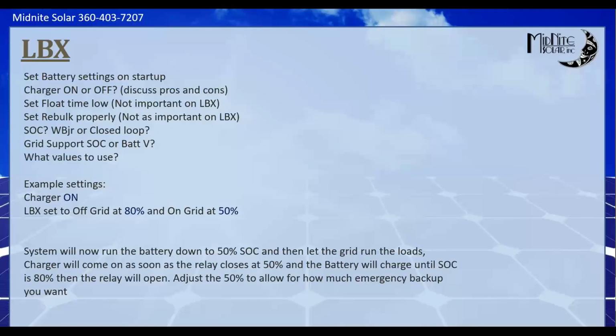I will say this: we've got one running in Oregon that's been running for over a year in grid support mode, and the utility came out the other day and said over the course of 12 months they have logged 0.14 kilowatt hours of selling from the Rosie, and they're monitoring 100 times a second. My utility in Florida has never noticed it at all, but you will get a couple nuisance bursts of selling when you're in a grid support mode in any inverter. It's just the nature of how grid support works.